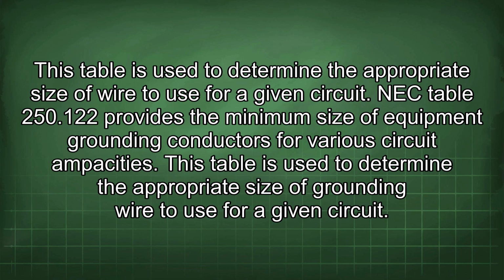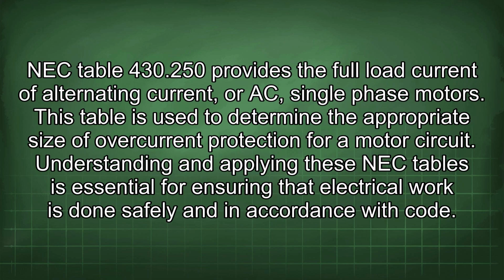NEC Table 250.122 provides the minimum size of equipment grounding conductors for various circuit ampacities. This table is used to determine the appropriate size of grounding wire to use for a given circuit. NEC Table 430.250 provides the full load current of alternating current (AC) single-phase motors. This table is used to determine the appropriate size of overcurrent protection for a motor circuit. Understanding and applying these NEC tables is essential for ensuring that electrical work is done safely and in accordance with code.